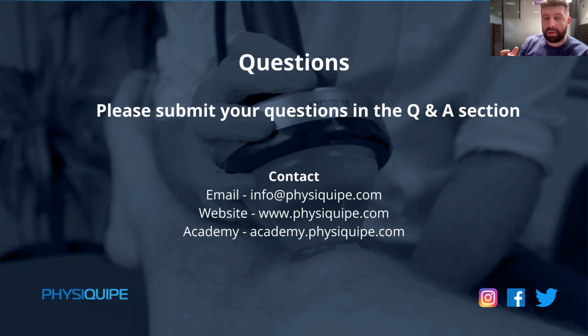If it gets quite angry at you, or if the patient says that was quite sore, which I've had one or two say it was quite sore for the next couple of days, it's like, okay, it might be a bit too soon. I might look at other management options. And maybe at the 6-week mark, when it feels like it's starting to settle a little bit, it's less reactive, we've managed the patient's load, then again, I'd start with low dose. When I say low dose, I mean things below 0.1 millijoules, which is going to be different for different devices in terms of what level it's on, and different therapy sources or applicators. So yeah, low doses, see how it responds, and then you build it up.